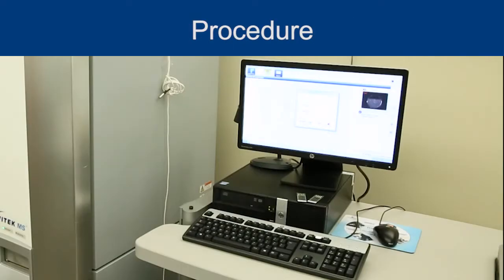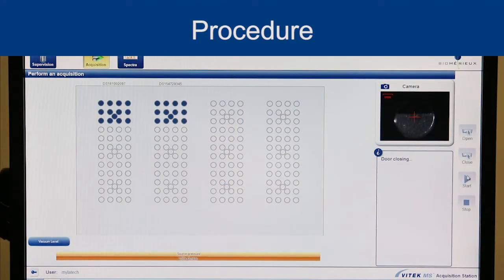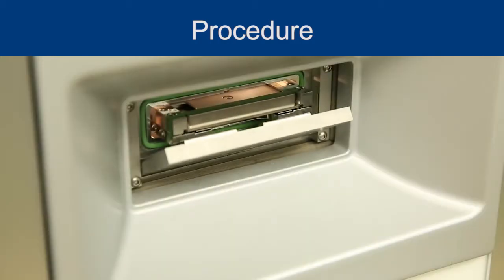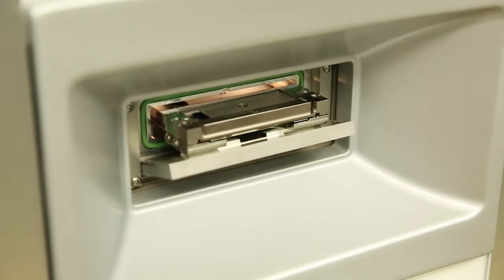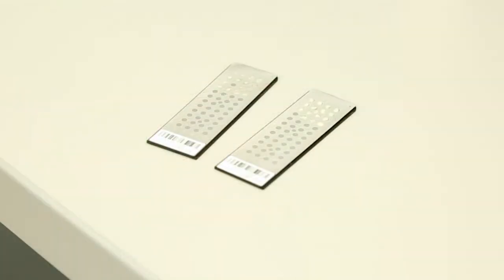The VITEK MS Acquisition Station software is used to monitor and display the instrument status, perform sample analysis activities, and can display previously acquired spectra.